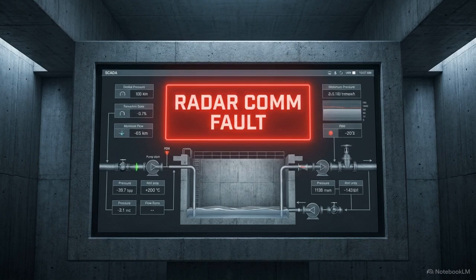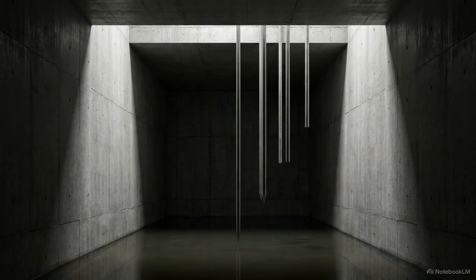If that continuous analog radar signal fails and the wet well runs dangerously dry, a physical fail-safe engages. A hardwired 4-point conductivity switch acts as a deadman circuit. When the water drops below the metal probes, the electrical circuit breaks, instantly tripping the pump to prevent dry running.